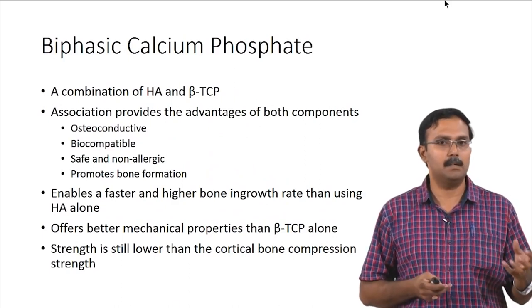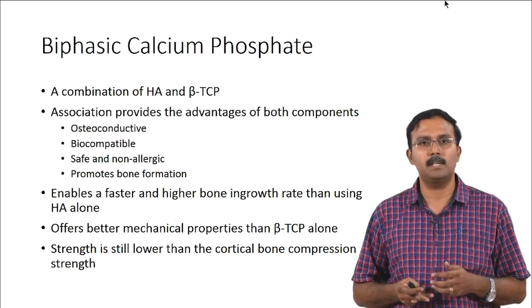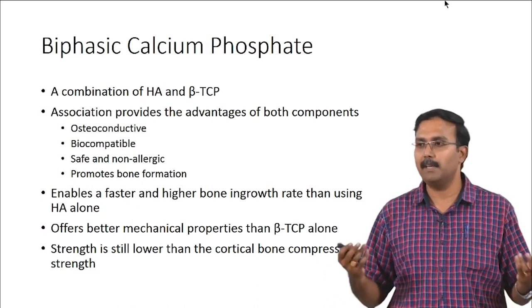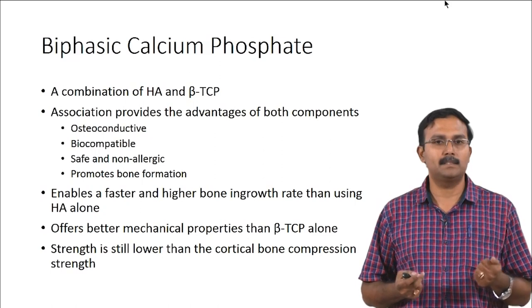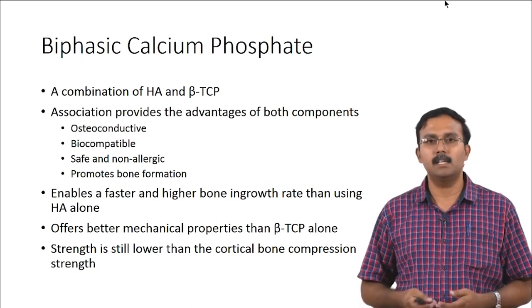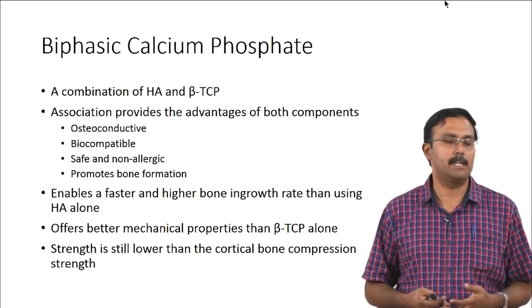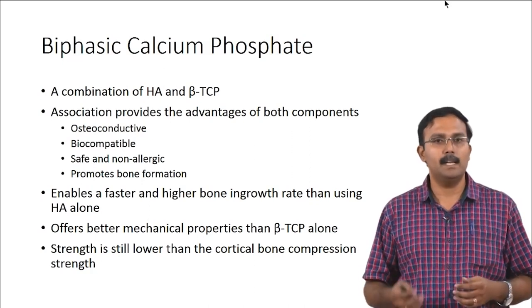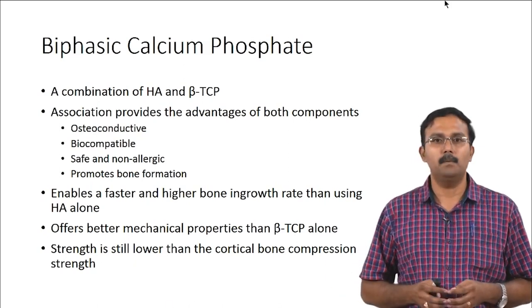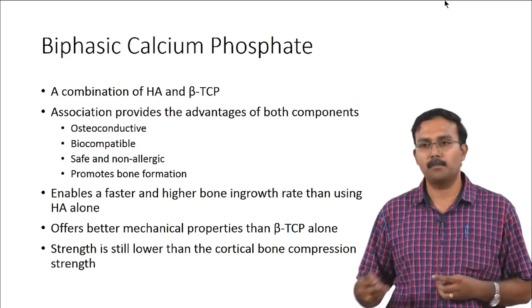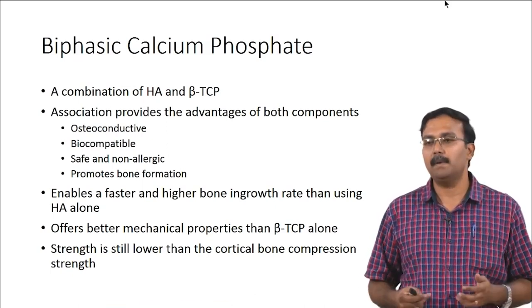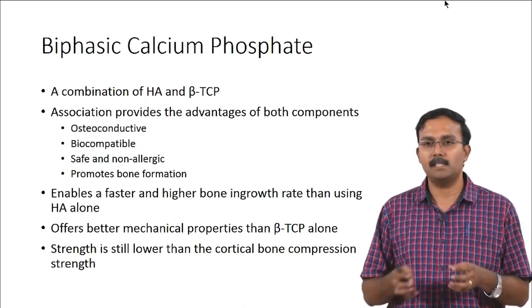Biphasic calcium phosphate is a combination of hydroxyapatite and beta tricalcium phosphate, and is preferred to using either independently. It has the advantages of both materials — it is highly osteoconductive, biocompatible, safe, and non-allergic. It promotes new bone formation, making it osteoinductive, and enables faster and higher bone ingrowth rate compared to hydroxyapatite alone. It offers better mechanical properties than beta tricalcium phosphate alone; however, strength is still lower than cortical bone compressive strength, so optimizing for desirable mechanical properties remains a challenge.